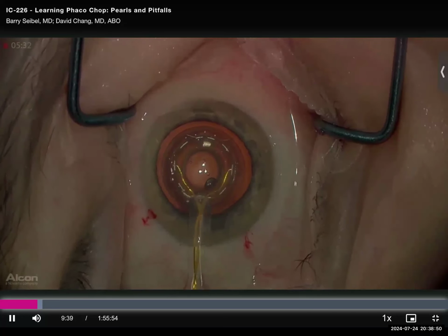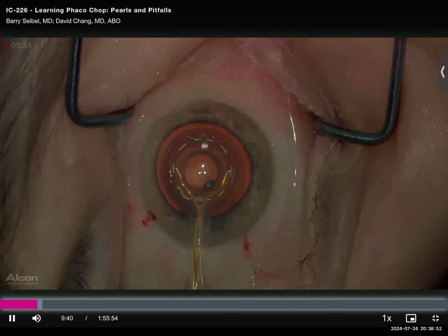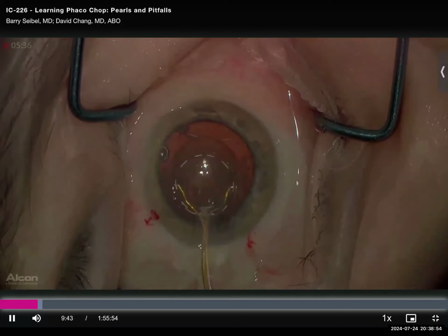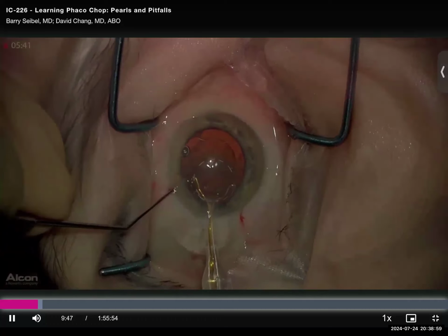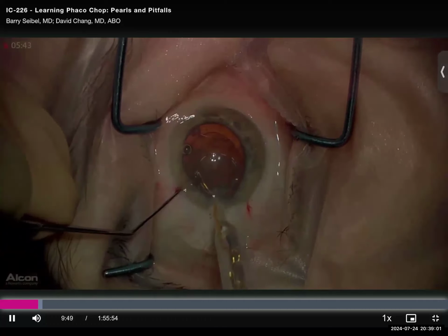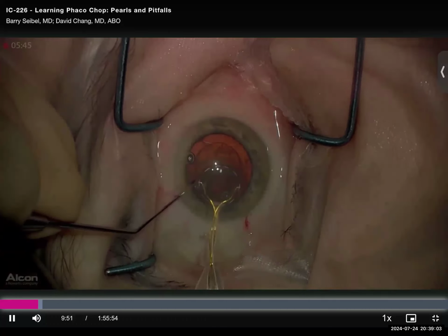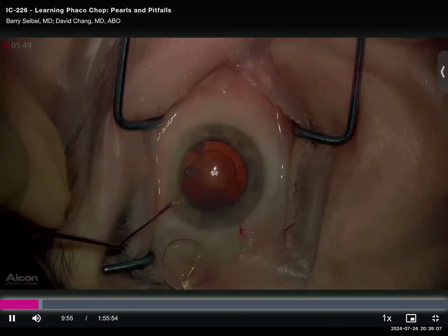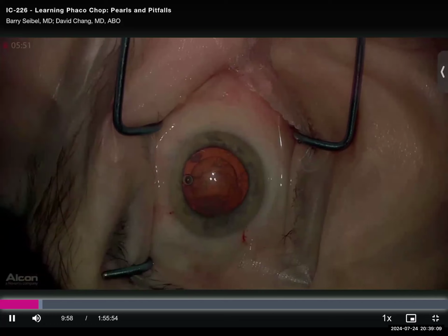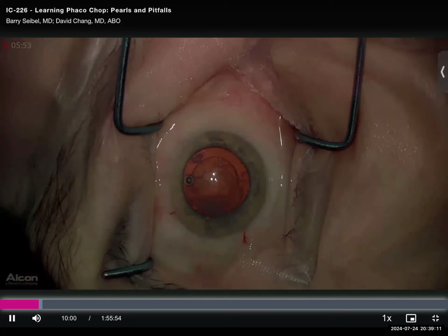I've applied suction. That was the cut, and instantaneously 360 degrees around, I release the suction, and I have a complete capsulotomy. So I think what's going to make this really nice now is they've developed a system where the vacuum you're going to use is from the phaco machine as well as the energy. So you'll be able to attach it to any phaco machine, and that's Zepto.